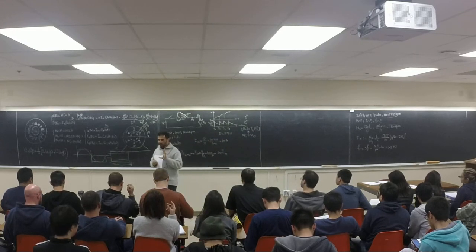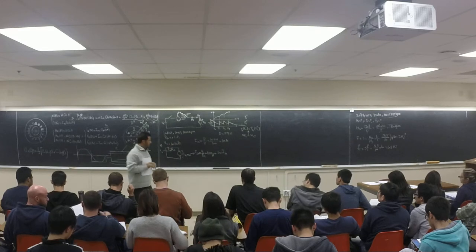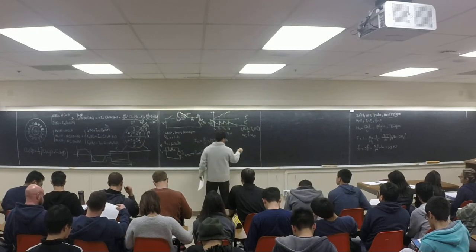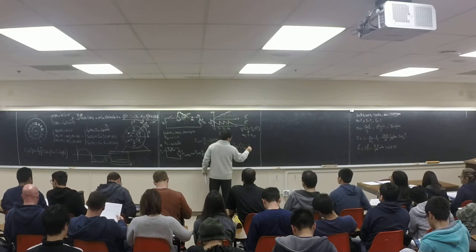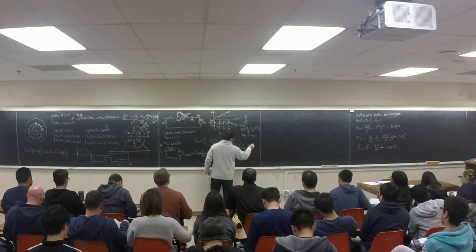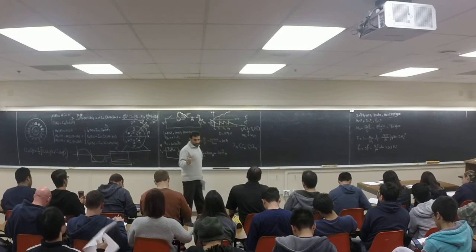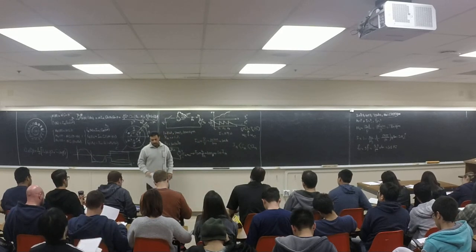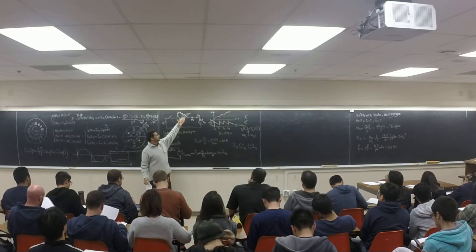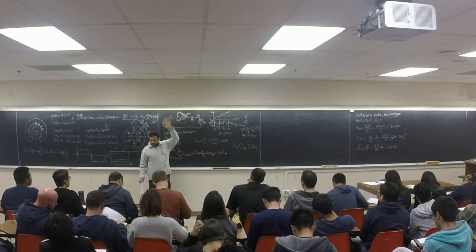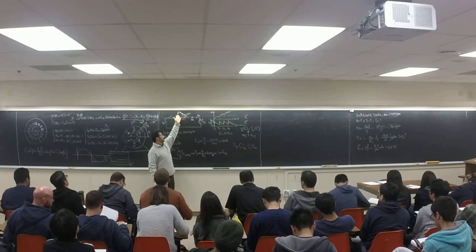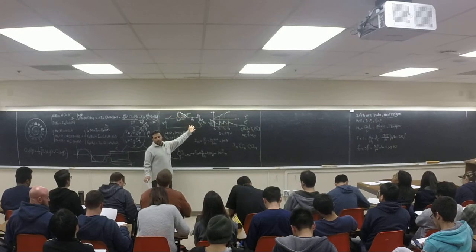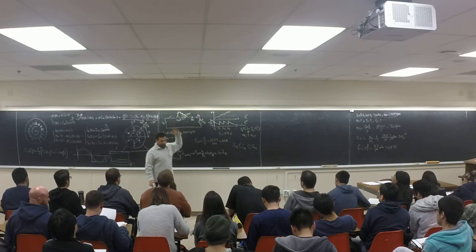I want to design a starter for this machine to limit the current. I want to limit the armature current between IN and 2IN during the start. That's my aim. So let's first calculate how much is the total resistance. I want to calculate RST1. I don't know how many we have. If we have 4, maybe RST1, RST2, RST3, RST4. I don't know how many we have, so I'm going to start with this.